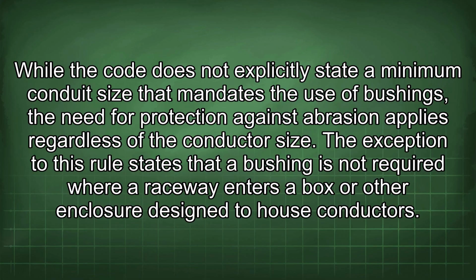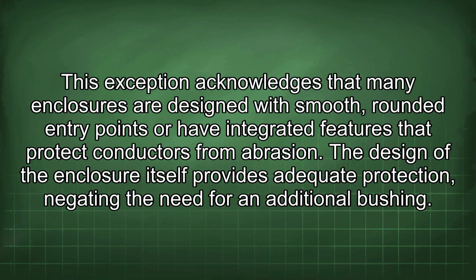The exception to this rule states that a bushing is not required where a raceway enters a box or other enclosure designed to house conductors. This exception acknowledges that many enclosures are designed with smooth, rounded entry points or have integrated features that protect conductors from abrasion. The design of the enclosure itself provides adequate protection, negating the need for an additional bushing.